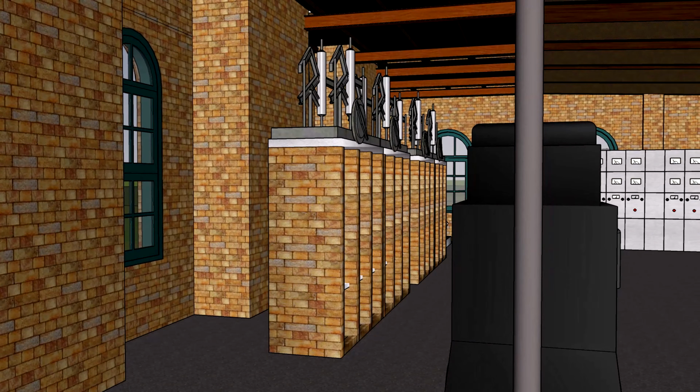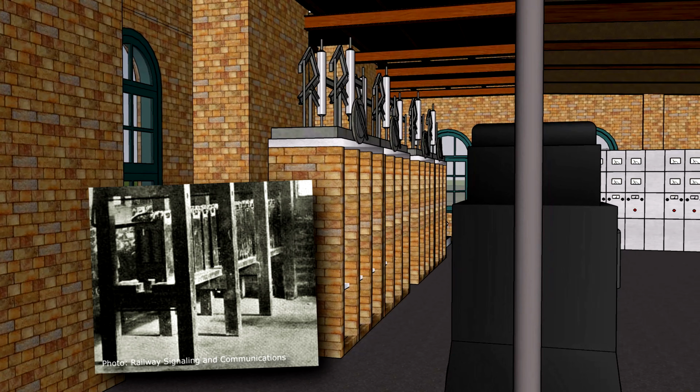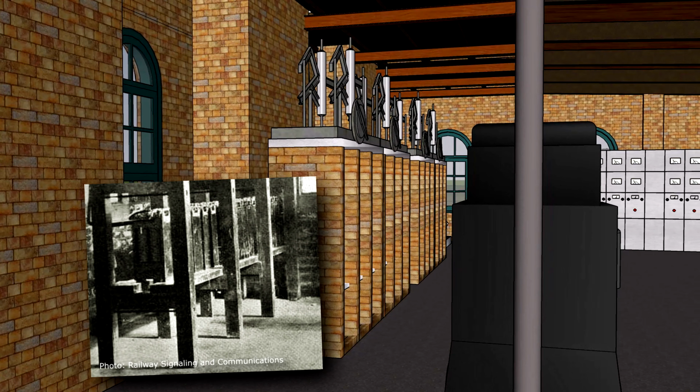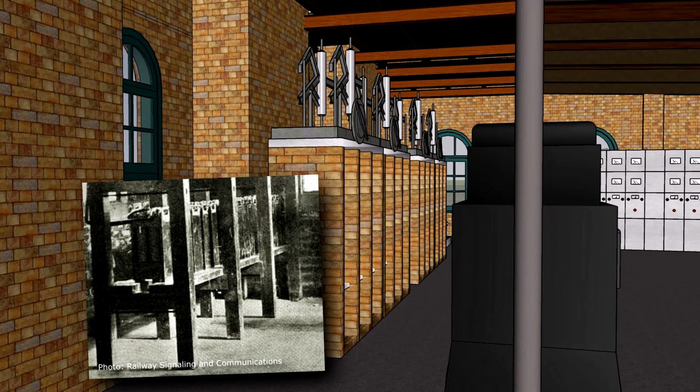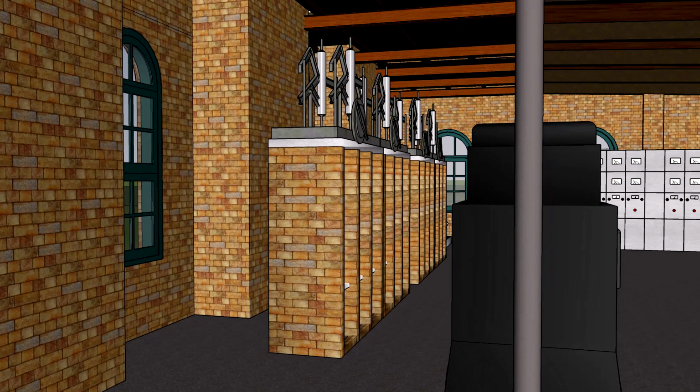The motors which drove the oil switches were DC powered, from current coming out of the rotary converters. When the rotary converters were down, or turned off, however, the switch motors could still be operated via a single 125-volt storage battery. This battery was initially kept within the rotary room on the main floor, but it was eventually moved to the basement due to the acidic fumes emanating from the battery.